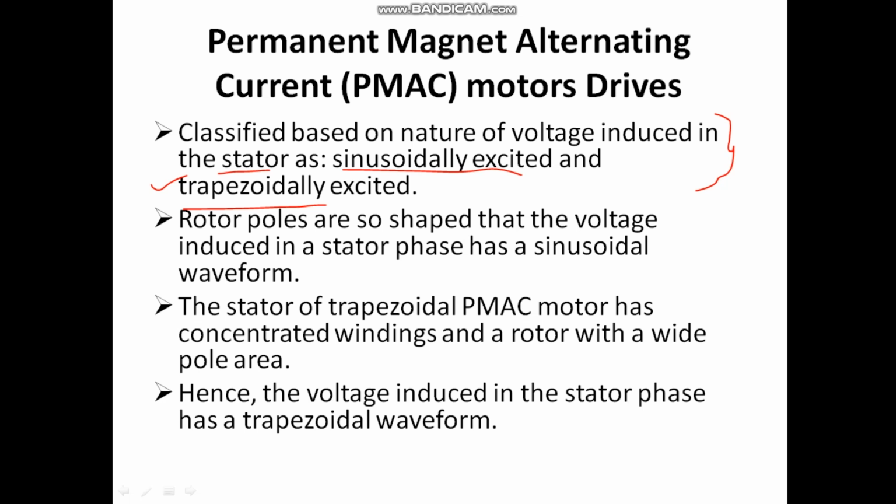right? So a sinusoidal PMAC has the distributed winding in the stator, right? It employs rotor geometries such as inset or interior, which if you can recall I had shown when I had drawn the synchronous motor drive, right? Now in such a sinusoidally excited PMAC, the rotor poles are so shaped that the voltage induced in the stator phase has a sinusoidal waveform, hence the name sinusoidal PMAC, right?